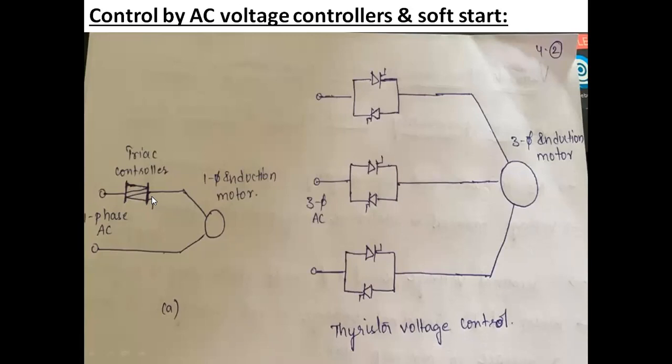We can attain the speed control by varying the triac firing angle. Like thyristors, these triacs also have firing angles. If you vary the firing angle of the triac, we can adjust the speed here. So speed control is obtained by controlling the firing angle of the triac. These controllers are called solid state fan regulators. These have very high efficiencies because losses are not there.